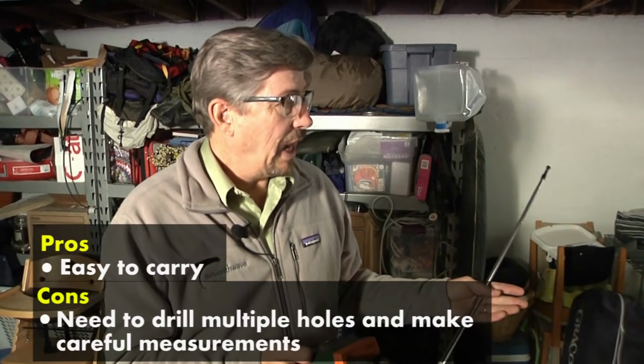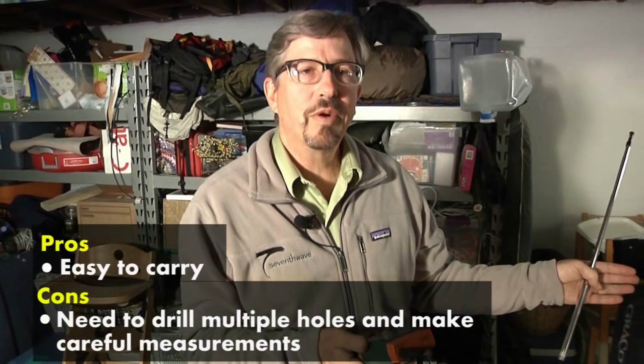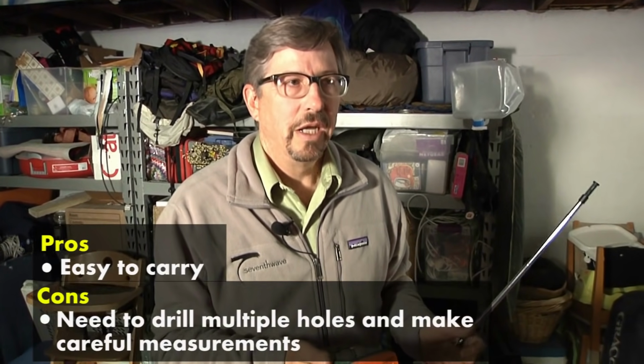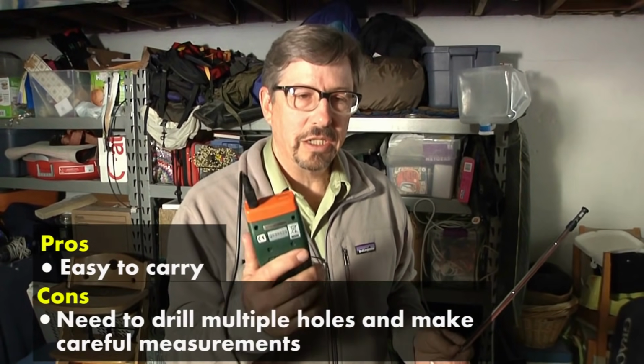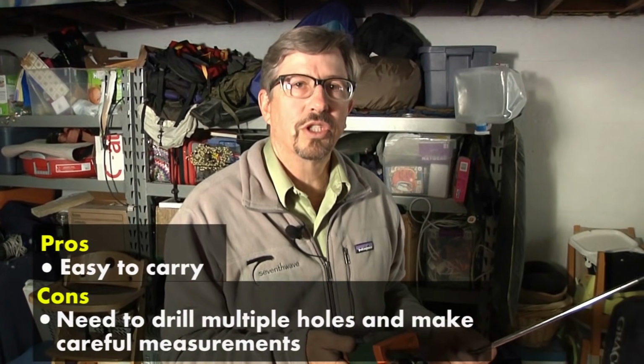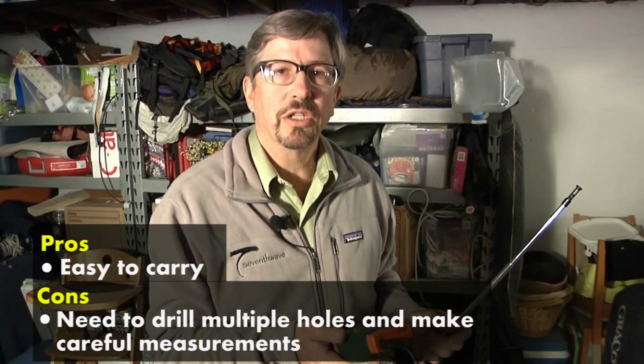But I can tell you that we saw everything from 190 feet per minute worth of velocity there to over 800 feet per minute. And one thing we can show you is, because this little unit can data log and we recorded those traverses, we'll show you a graph of what those 5 velocity traverses look like.